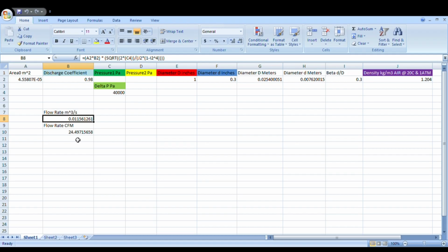So the two parameters I'm using to start the design are the full scale range of the pressure transducer and the maximum flow rate the Venturi can measure. I'll say about 25 CFM is the most I want to measure, and the pressure drop across the Venturi will be no more than 40,000 pascals, correlating to roughly 25 CFM.